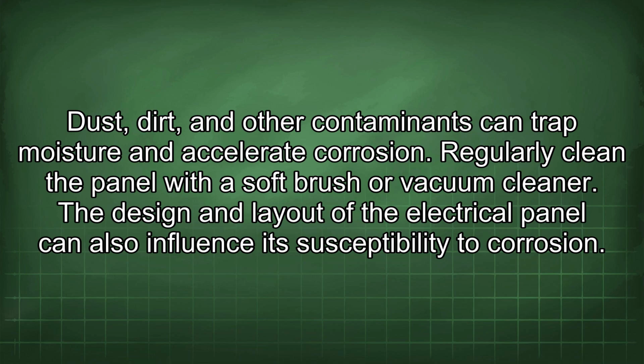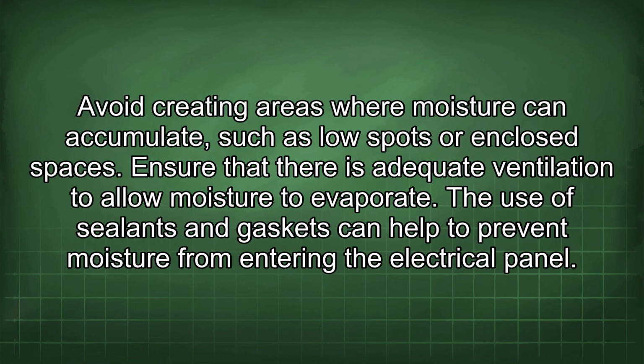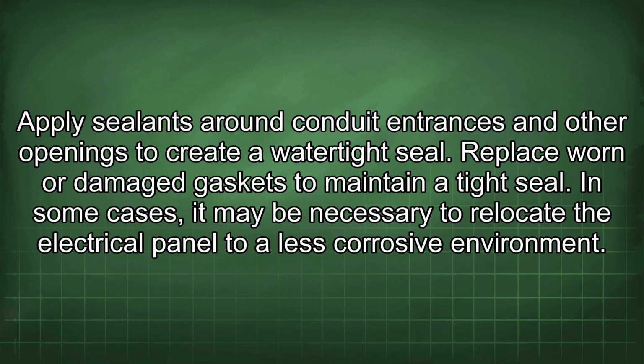The design and layout of the electrical panel can also influence its susceptibility to corrosion. Avoid creating areas where moisture can accumulate, such as low spots or enclosed spaces. Ensure that there is adequate ventilation to allow moisture to evaporate. The use of sealants and gaskets can help to prevent moisture from entering the electrical panel. Apply sealants around conduit entrances and other openings to create a watertight seal. Replace worn or damaged gaskets to maintain a tight seal.